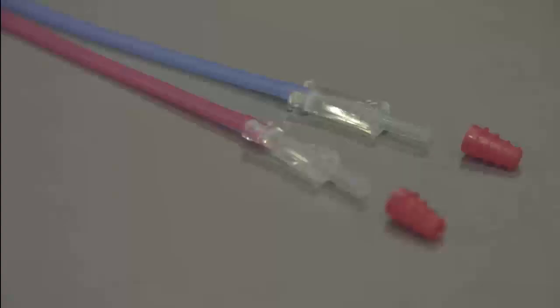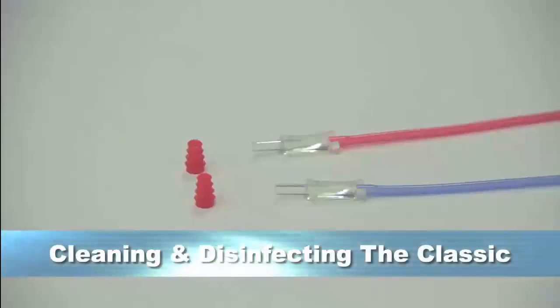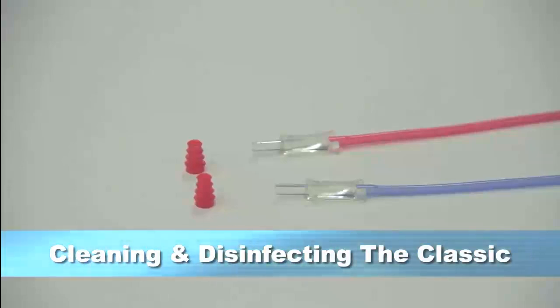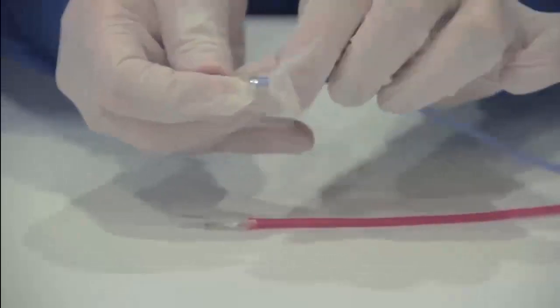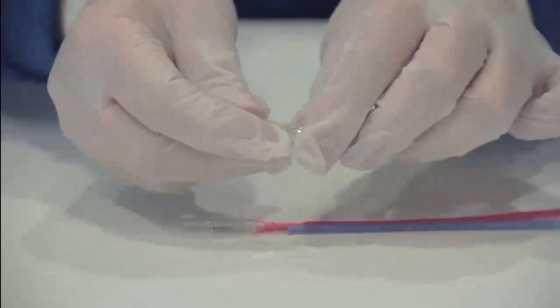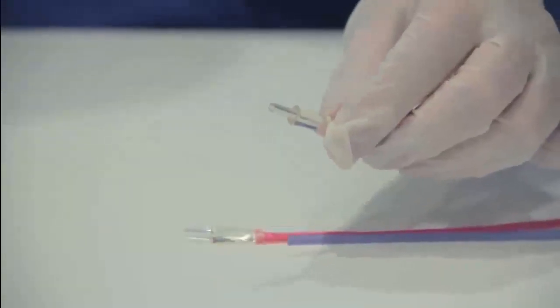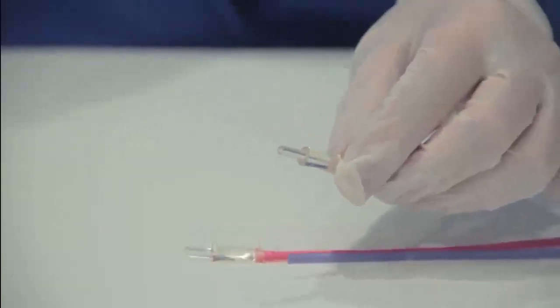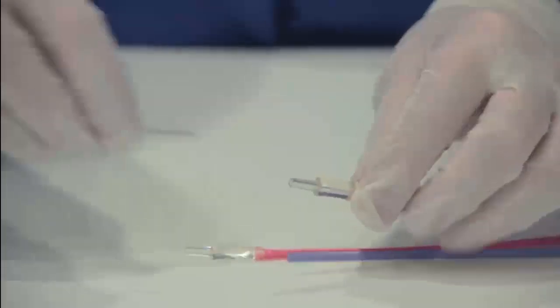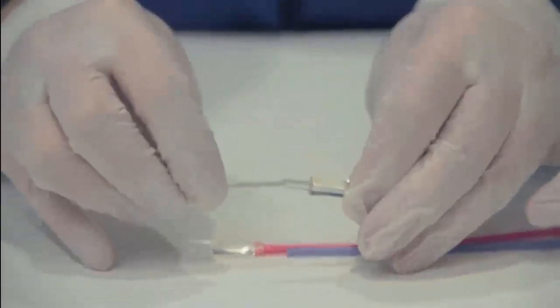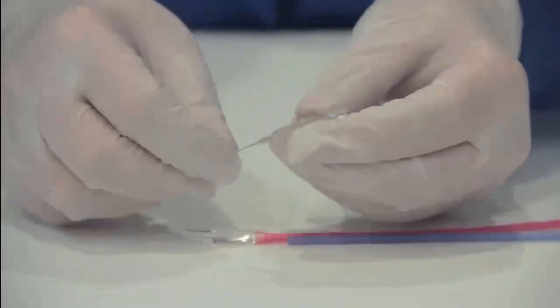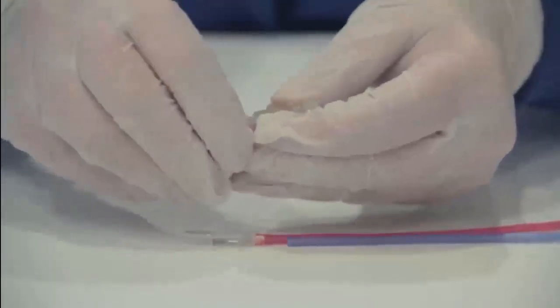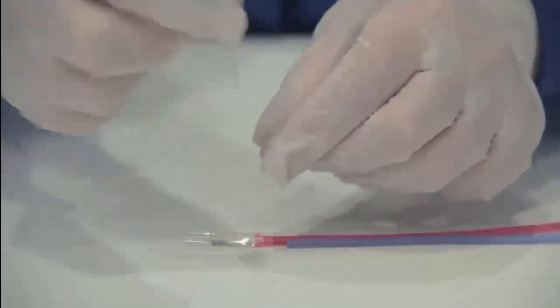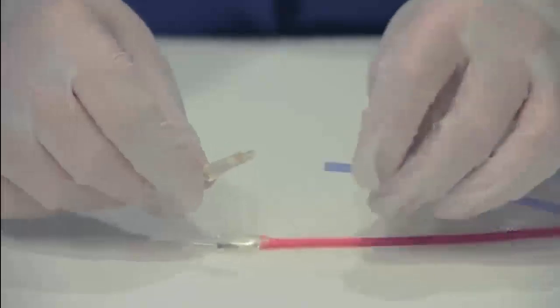The MB11 Classic uses disposable electrodes and disposable ear cups or ear tips. These disposables are intended for single baby use and should be discarded. If ear tips are used, the clear ear tip adapter should be examined for the presence of debris inside the adapter after use on each baby. If debris is present, the adapter should be removed from the tubing and the adapter cleaning brush should be used to remove the debris. After cleaning, reattach the adapter to the tube.